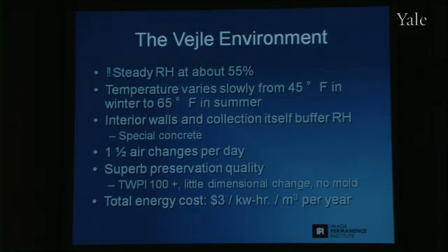And as far as quality goes, the TWPI is over 100. Here in Sterling, most of the TWPIs are about 50, 55. There's very little dimensional change because the RH hardly varies at all throughout the year. There's no mold because 55% RH won't support mold.